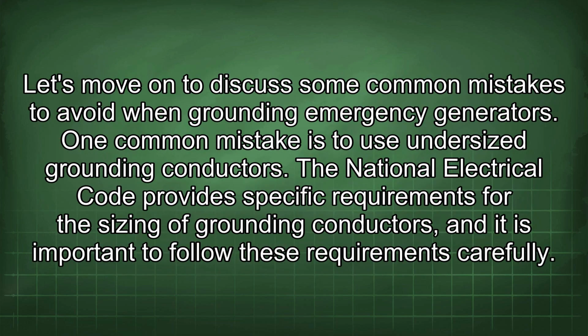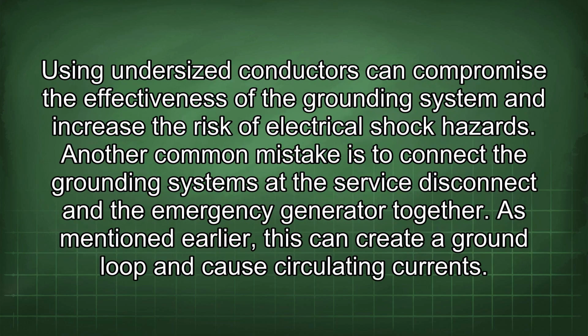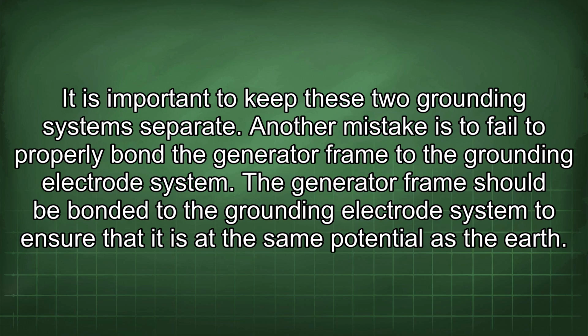Let's move on to discuss some common mistakes to avoid when grounding emergency generators. One common mistake is to use undersized grounding conductors. The National Electrical Code provides specific requirements for the sizing of grounding conductors, and it is important to follow these requirements carefully. Using undersized conductors can compromise the effectiveness of the grounding system and increase the risk of electrical shock hazards. Another common mistake is to connect the grounding systems at the service disconnect and the emergency generator together. As mentioned earlier, this can create a ground loop and cause circulating currents. It is important to keep these two grounding systems separate.